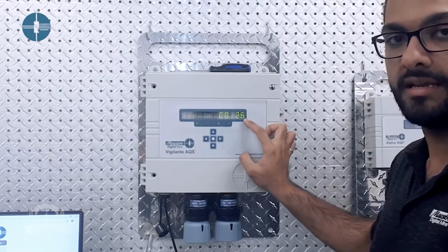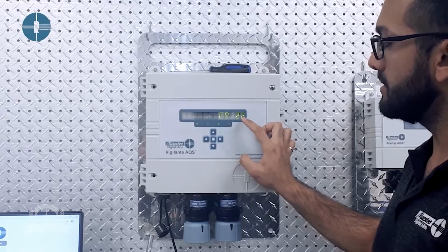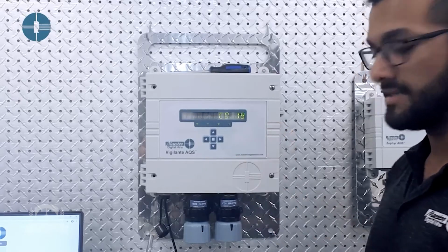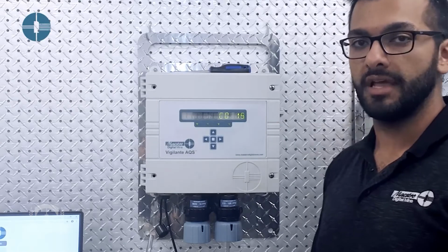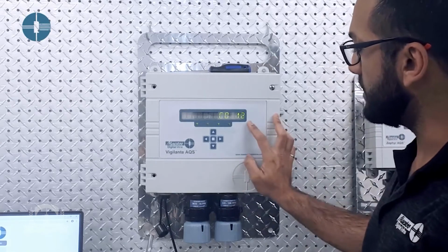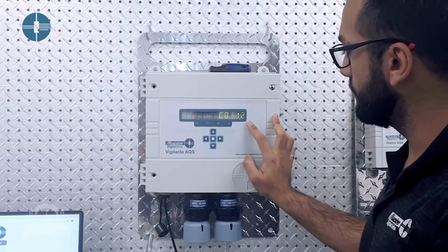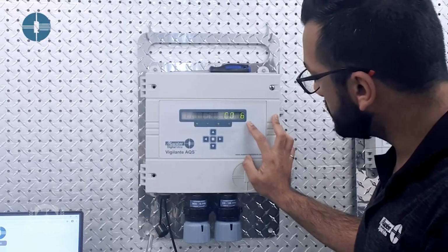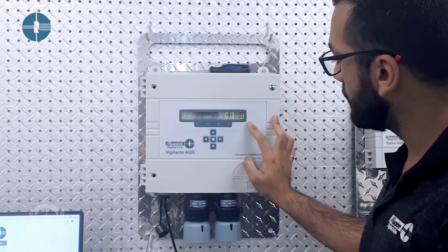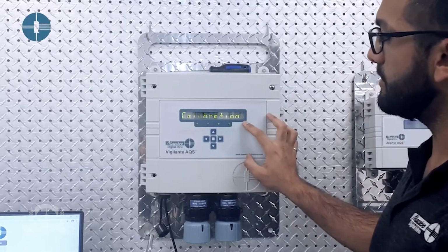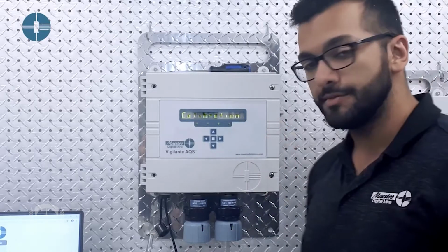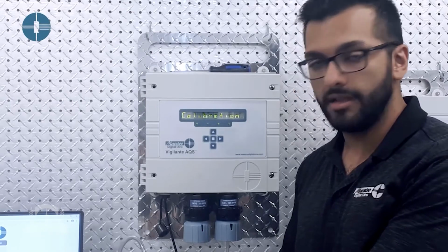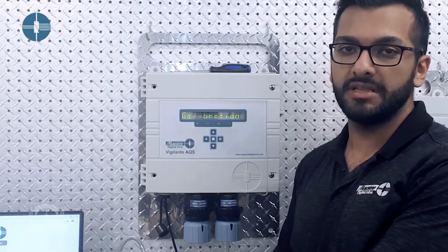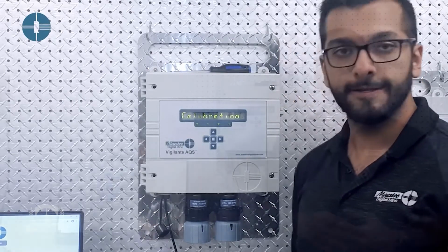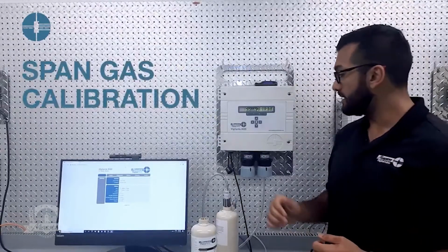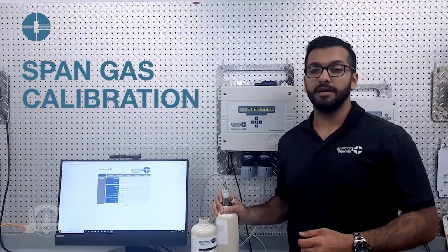Once this timer has ended, you'll be taken back to the calibration page, and that's the end of the zero calibration for the gas sensor. So we'll just wait for the timer to finish. Just have 6 more seconds. And there you go. Now you're prompted back to the calibration page. At this point, you can turn off your regulator for the zero gas, and you can repeat the steps for the calibration gas. So now that we've completed a zero calibration, we're going to move on to a span calibration.